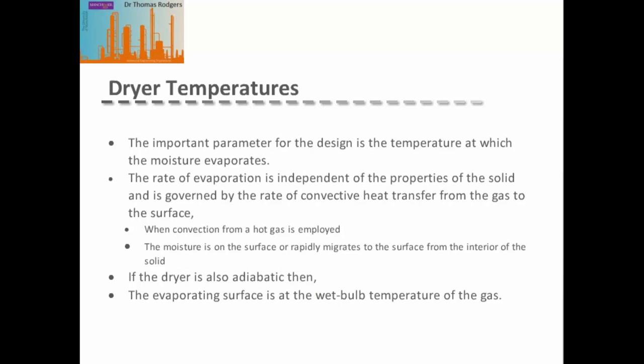The important parameter for dryer design is the temperature at which the moisture evaporates. If a convective hot gas heats the material and the moisture is on the surface or rapidly migrates to the surface from the interior, the rate of evaporation is independent of the solid's properties and is governed only by convective heat transfer from the hot gas to the liquid surface. Under adiabatic conditions, the evaporating surface is at the wet bulb temperature of the gas.